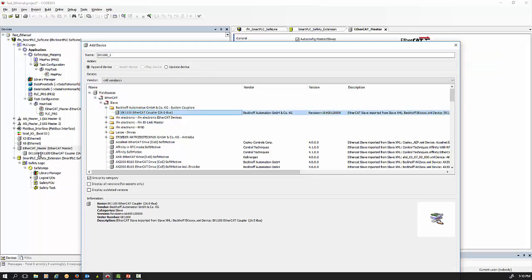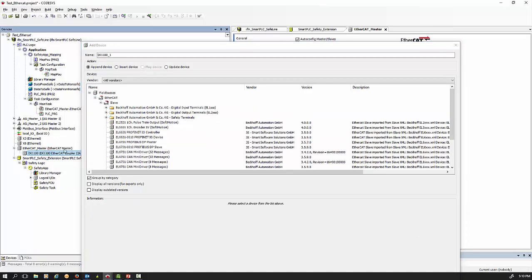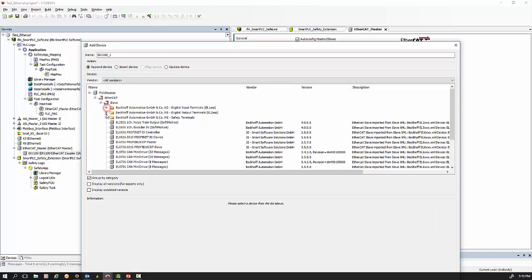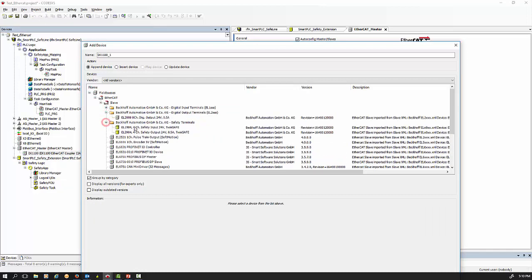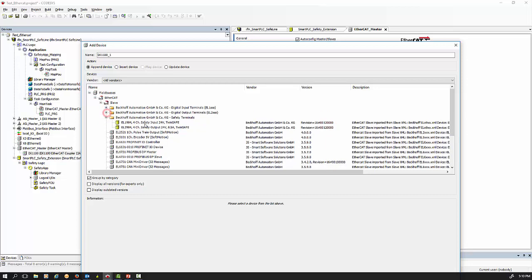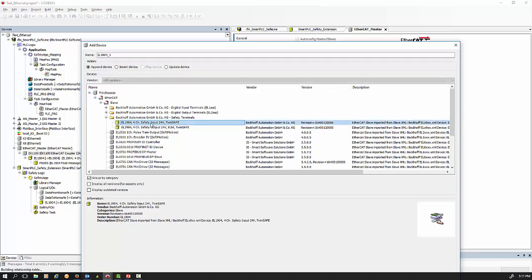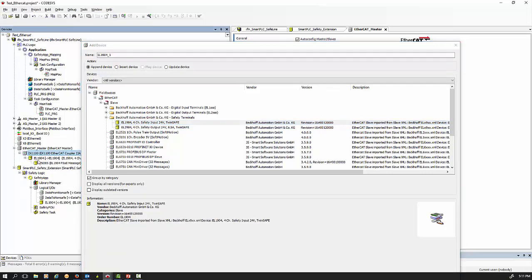Once you have the ESI files installed, right-click and say 'add device', then go to the EtherCAT coupler unit — the main unit — and double-click. You'll see it adds the EtherCAT coupler. Then click on the EtherCAT coupler and add the slaves in sequence: first the safety input channel module. Notice that once you add it, it appears in both the safety world and the non-safe world.